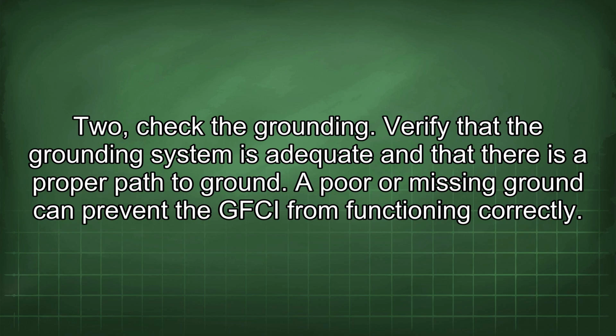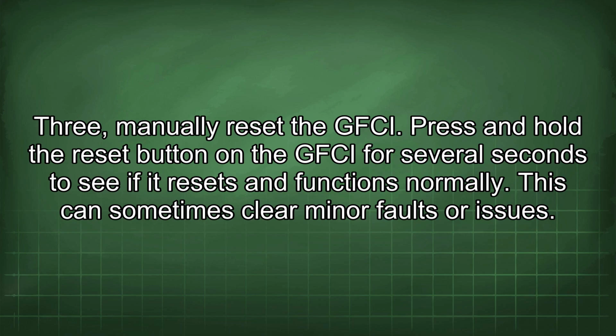2. Check the grounding. Verify that the grounding system is adequate and that there is a proper path to ground. A poor or missing ground can prevent the GFCI from functioning correctly. 3. Manually reset the GFCI. Press and hold the reset button on the GFCI for several seconds to see if it resets and functions normally. This can sometimes clear minor faults or issues.